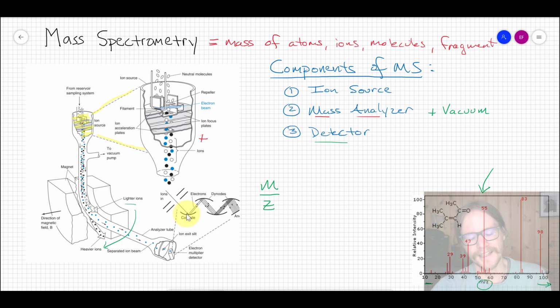So an ion comes in and it dislodges an electron here, and we get some electrons that come flying off the cathode, and then the next dynode is biased positive relative to this first one, more positive, and so those electrons come flying down further. This one's biased even more positive, so on and so forth. And so you start with, hypothetically, a single ion that strikes the first cathode, and as it cascades through the chain of dynodes, it gets amplified such that when it hits the final plate over here, this should say anode, this is measured.